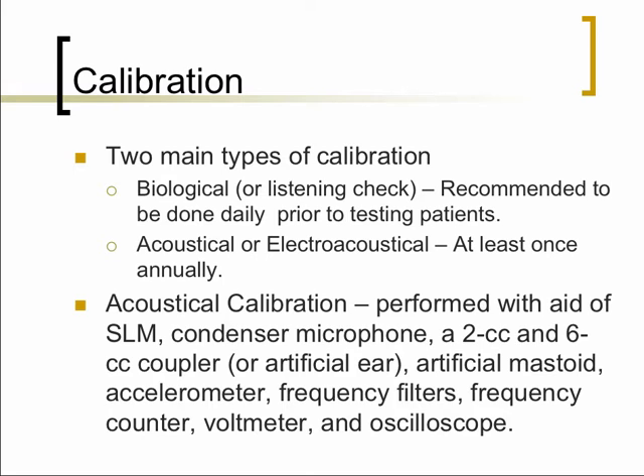For example, our VA clinic calibrates all their equipment twice a year, so once in every 6 months. So this acoustical calibration, the more detailed calibration, is done with the whole array of equipment. Of course, the star of all that you would use for calibration would be your sound level meter, along with a condenser microphone or a microphone.